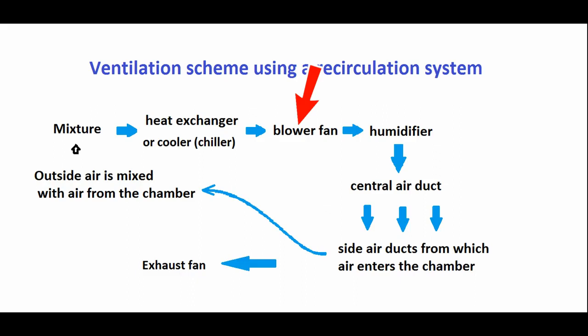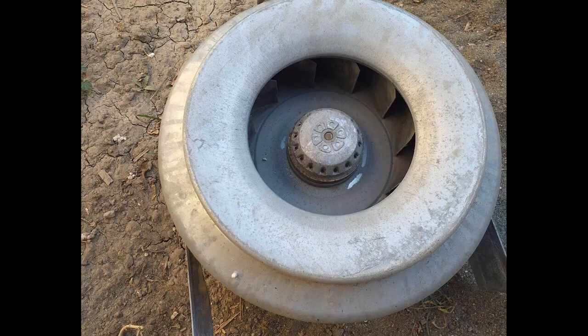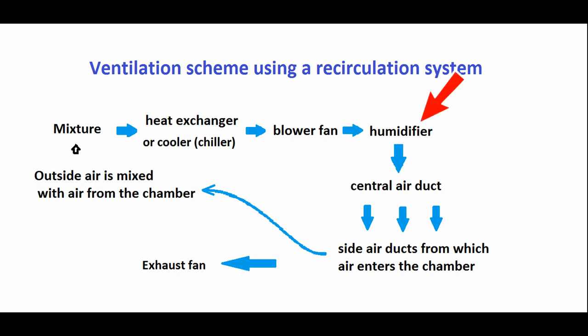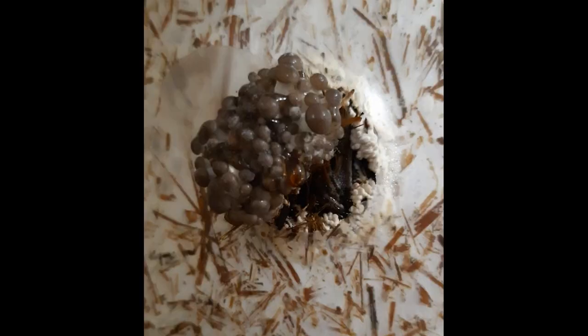The fan sucks this air through the pipe into the duct. The fan must be centrifugal — you can use a duct centrifugal fan, or the type called a snail in our country. After the fan is a humidifier. The air must be humidified before entering the central duct. If humidifiers are located in the chamber itself separately from the air flow, then dry air from the air duct and separately drip moisture will flow to the mushrooms — small mushrooms will die from condensation and those that have grown a little will dry.